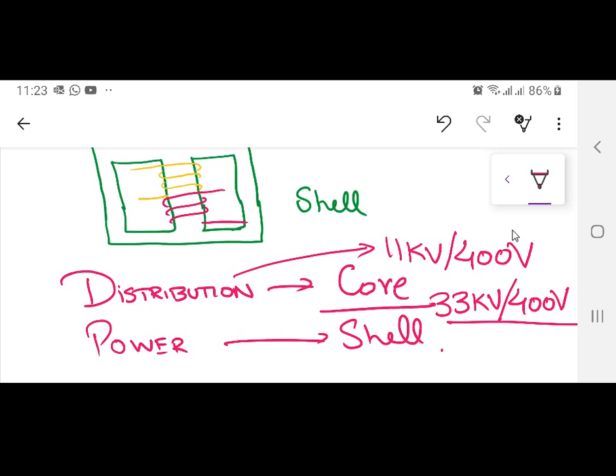Primary current will be less, the low or high voltage winding current will be less, so current is less, I square R losses are less. But there is a disadvantage also: 33 kV is a higher voltage, you will require more insulation.